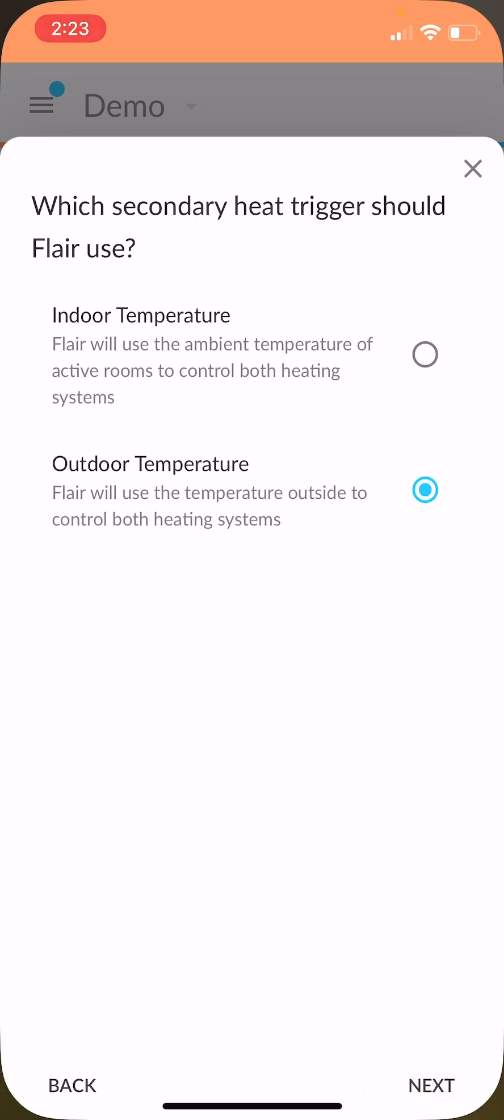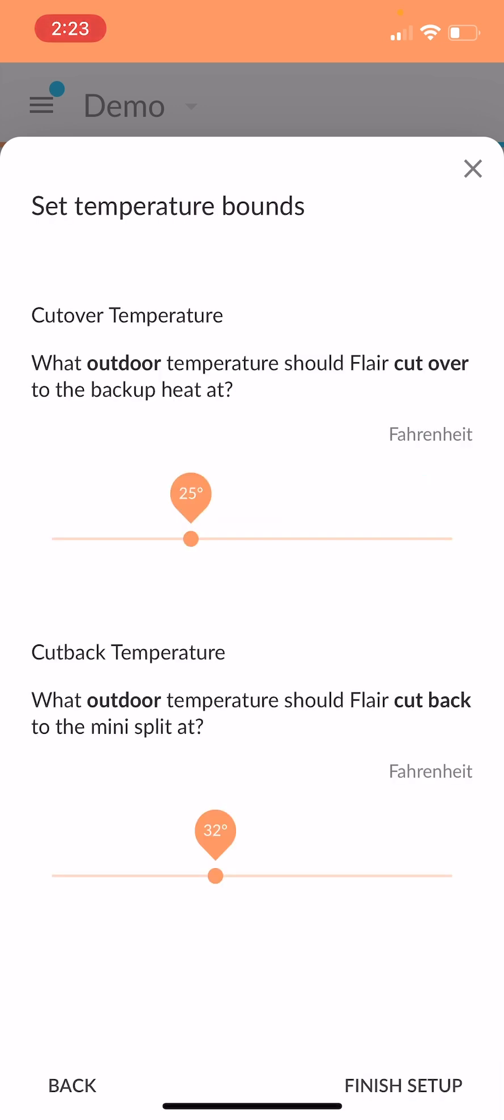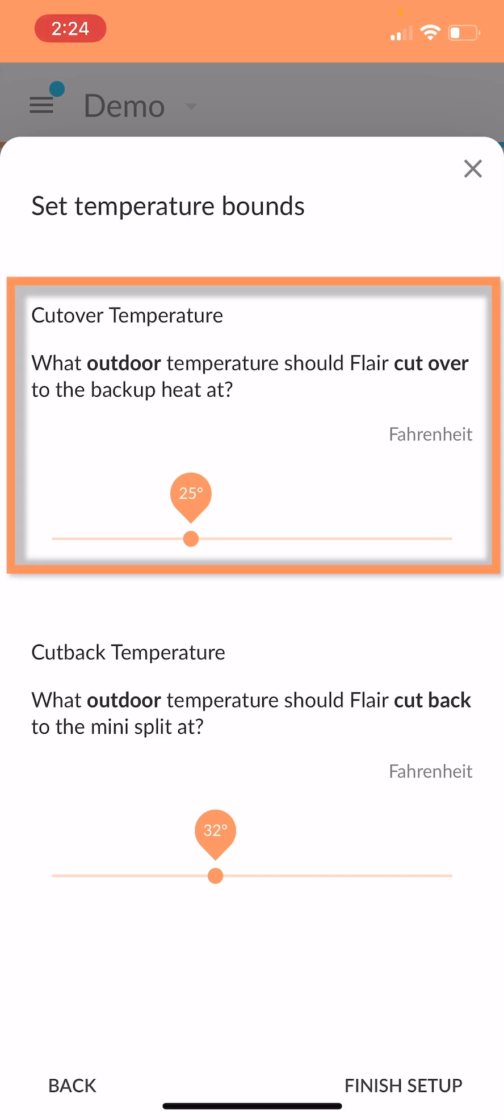Now, instead of using like a deadband and a balance point, we use more of a cutover temperature and a cutback temperature. Cutover is the temperature that the backup heat will or the second stage heat will engage at. So that's when we'll do the stage shifting right over to the second stage, either as a supplement or exclusively as the heating source.